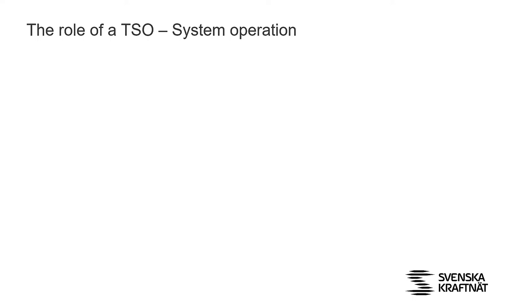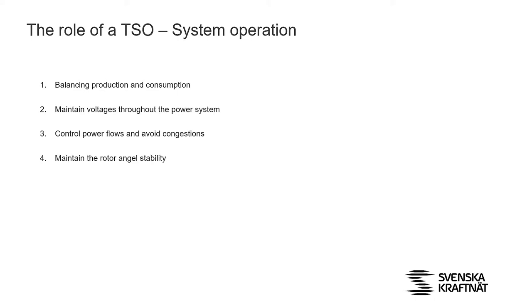So, what is a TSO? What are the system responsibilities? We have four golden steps. We are in charge of keeping the balance in the system between production and consumption in the short term. We also maintain voltage throughout the power system. We need to control power flows and avoid congestions to make sure we can transport power from A to B. We need to maintain rotor angle stability to make sure we have no oscillations in the power system. These are the four main steps, and we must also be able to restore the system if we fail with one or several of them.